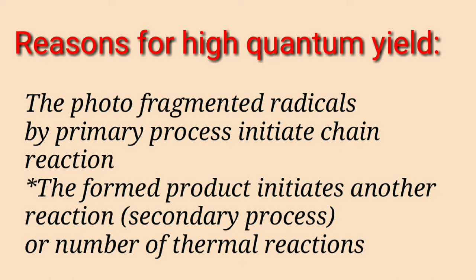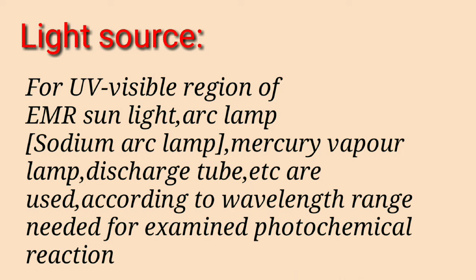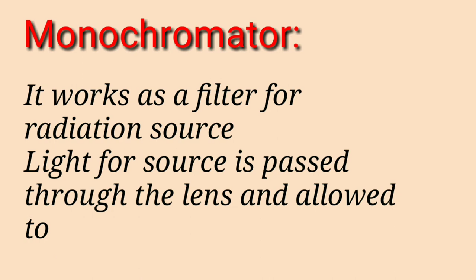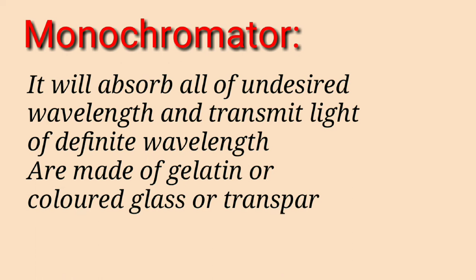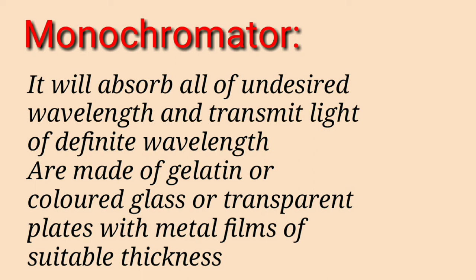Light source. For the ultraviolet visible region of electromagnetic radiation, sunlight, arc lamp, sodium arc lamp, mercury vapor lamp, discharge tube, etc. are used, according to the wavelength range needed for the examined photochemical reaction. Second is the monochromator. A monochromator works as a filter for the radiation source. When light from the source is passed through the lens and allowed to pass through it, it will absorb all of the undesired wavelengths and transmit light of a definite wavelength. Monochromators are generally made up of gelatin or colored glass or transparent plates with metal films of suitable thickness.